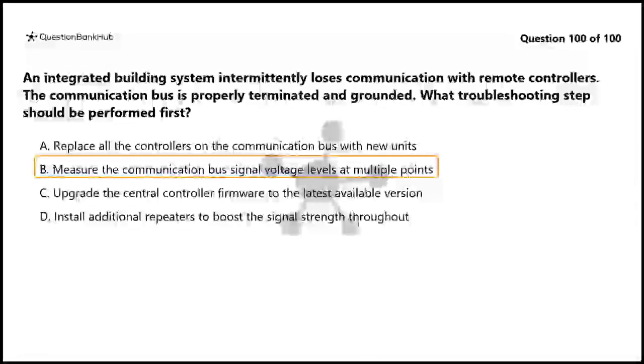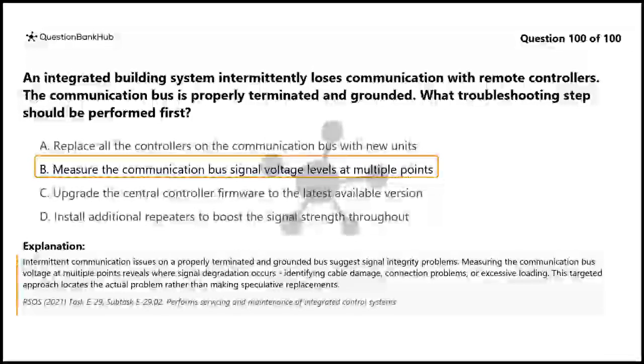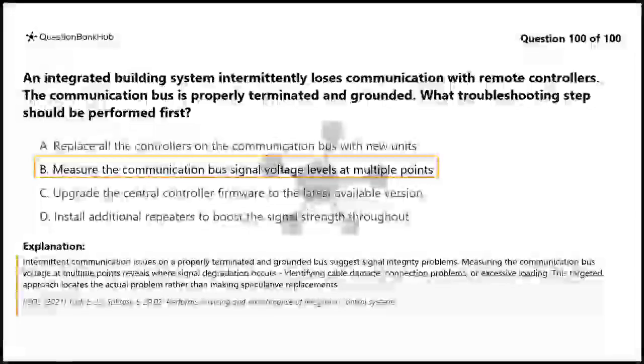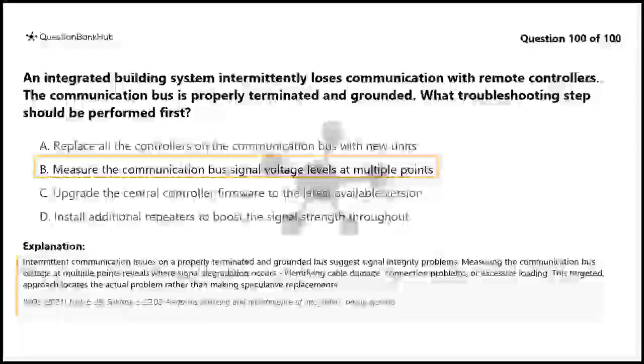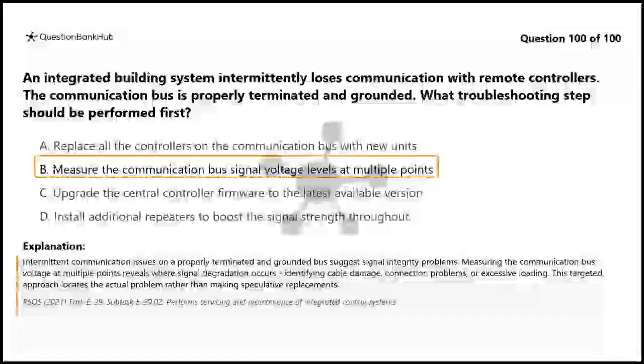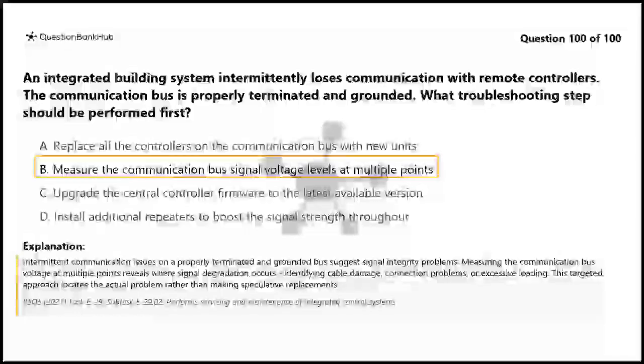The correct answer is B. Measure the communication bus signal voltage levels at multiple points. Intermittent communication issues on a properly terminated and grounded bus suggest signal integrity problems. Measuring the communication bus voltage at multiple points reveals where signal degradation occurs, identifying cable damage, connection problems, or excessive loading. This targeted approach locates the actual problem rather than making speculative replacements.